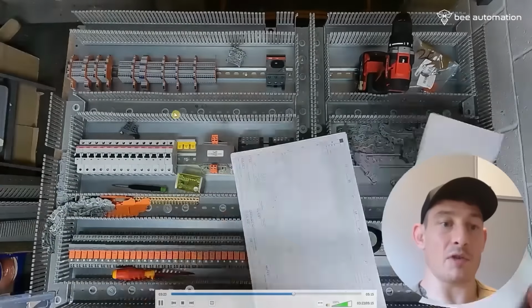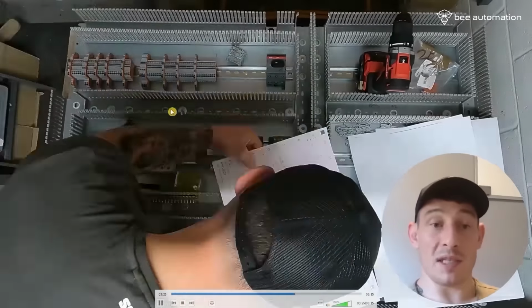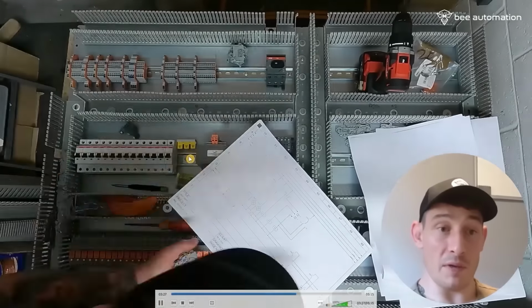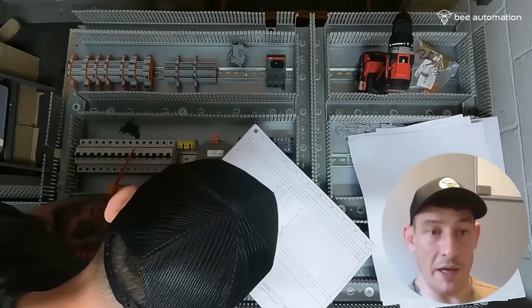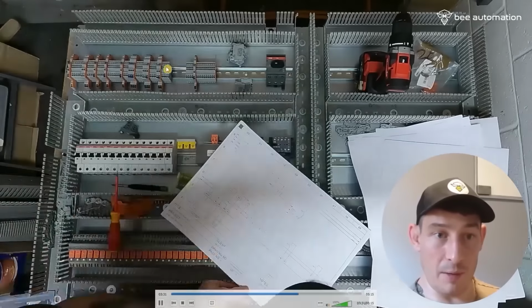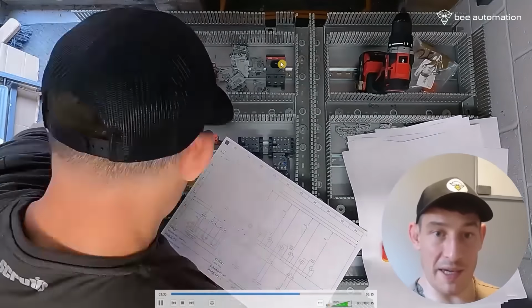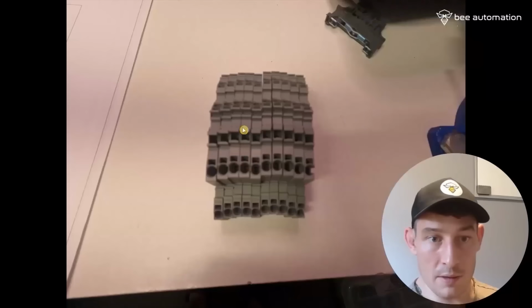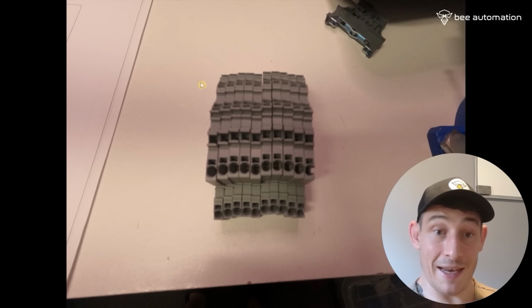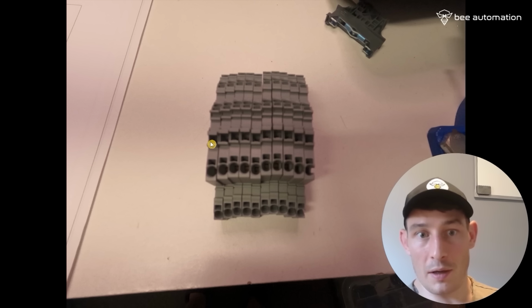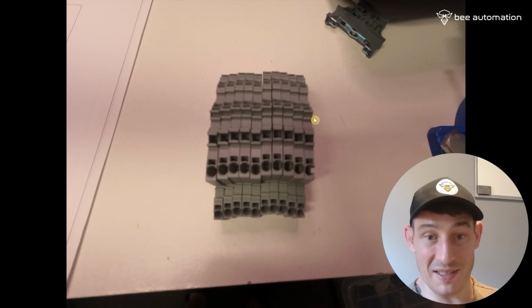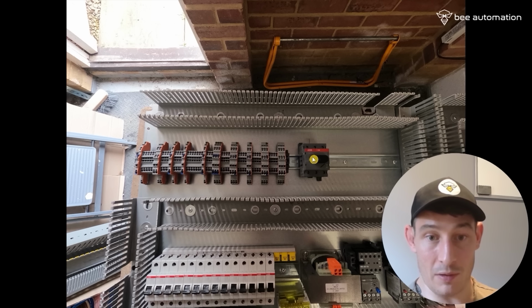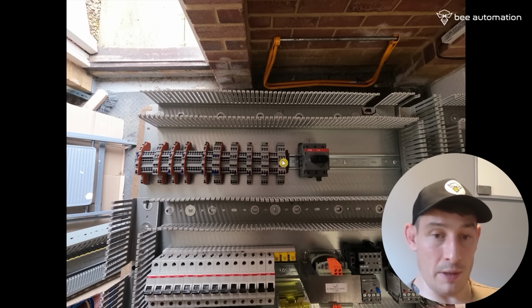Now I'm replacing those two single terminal blocks with one of the double terminal blocks from Wago, creating some space to move things along. I ended up using 10 double terminals, which saved me 10 single terminal blocks' worth of space on the DIN rail, and as you can see, that leaves a bit of room if we need to add additional terminal blocks.